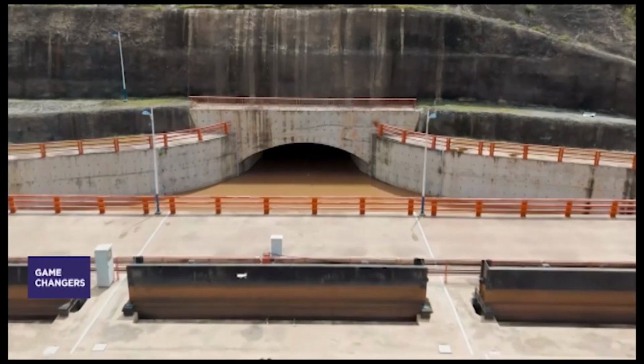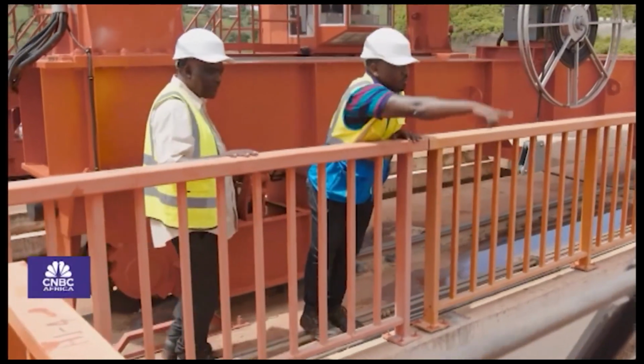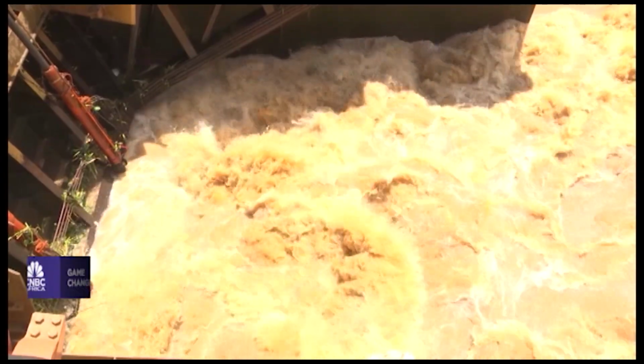If you see the design here at the intake, there are 5 stop logs, which allow the water to go to the tunnel, up to the inlet chamber. From here to the inlet chamber is almost 700 meters. The inlet chamber is the place where it distributes to the different penstocks. We have 3 penstocks, we have 3 machines. There the water starts to have high velocity. There is a head, so we increase the velocity in order to have the impact on the runner. It goes up to the powerhouse.